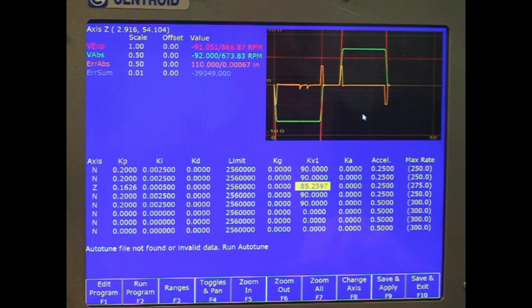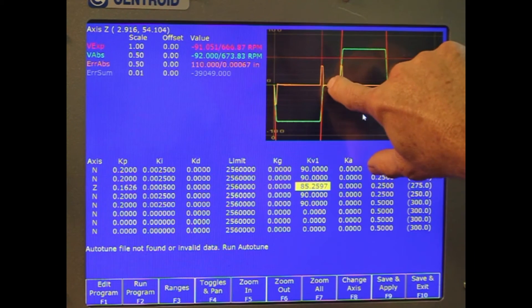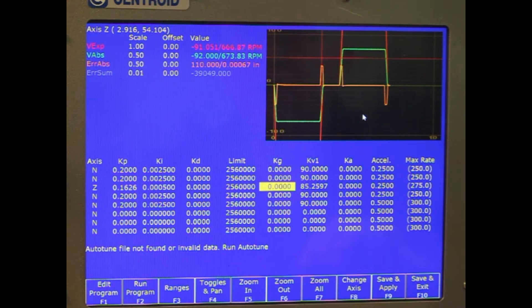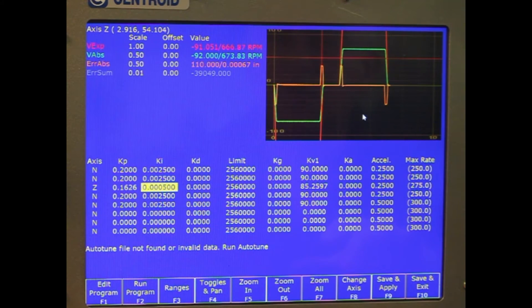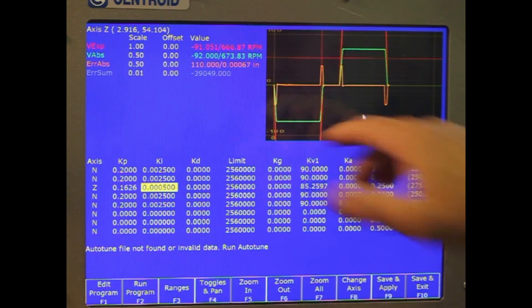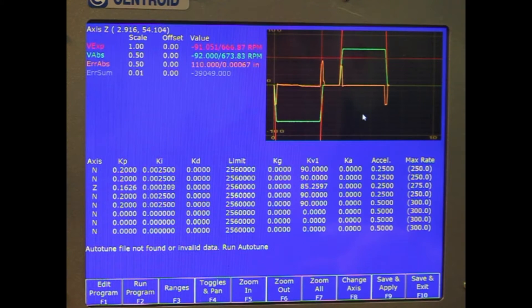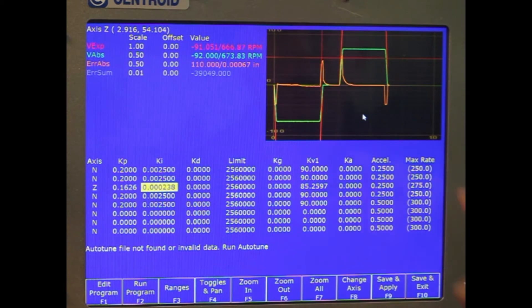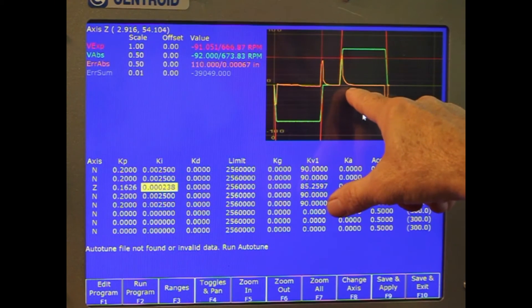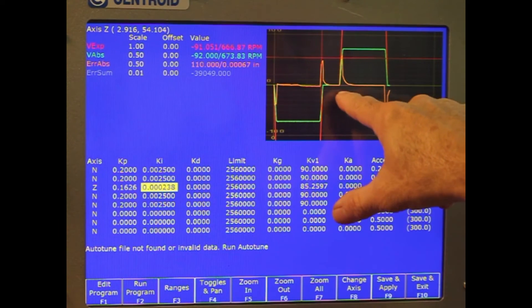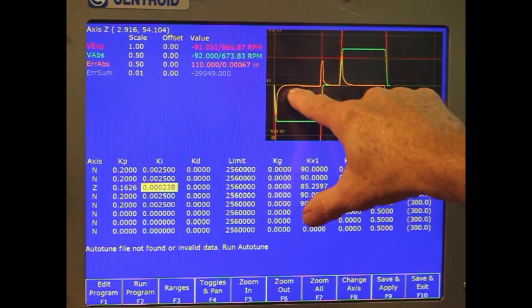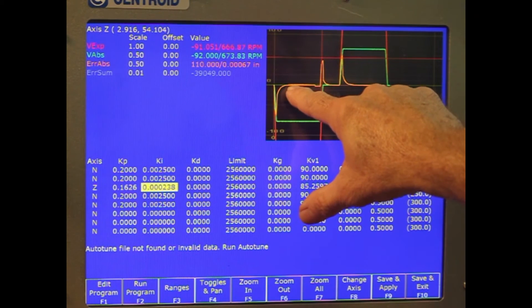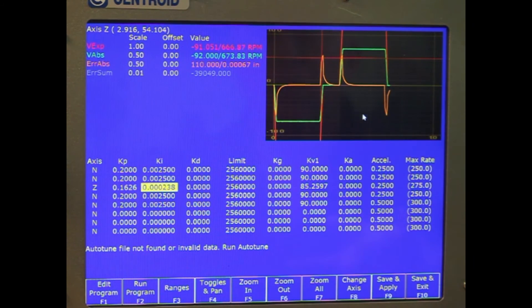Now that looks pretty decent. The KI is the integral, more of a time base. And if I lower that, you'll see it kind of mushes out a little bit. And it takes longer for it to actually, once it gets out of position, it's taking almost a full second before it gets down to zero error.